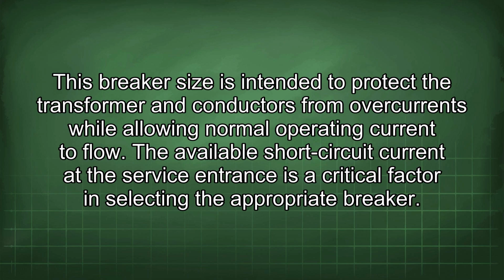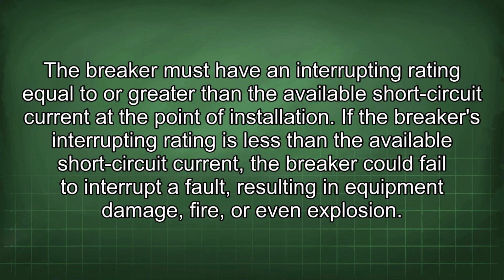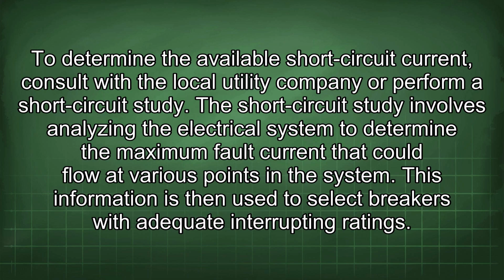The available short circuit current at the service entrance is a critical factor in selecting the appropriate breaker. The breaker must have an interrupting rating equal to or greater than the available short circuit current at the point of installation. If the breaker's interrupting rating is less than the available short-circuit current, the breaker could fail to interrupt a fault, resulting in equipment damage, fire, or even explosion. To determine the available short-circuit current, consult with the local utility company or perform a short-circuit study. The short-circuit study involves analyzing the electrical system to determine the maximum fault current that could flow at various points in the system. This information is then used to select breakers with adequate interrupting ratings.